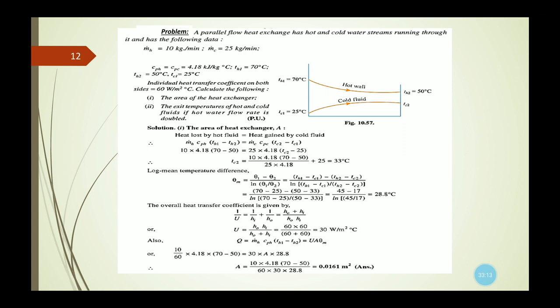Q can be represented mathematically in terms of the hot fluid parameters as m dot h cph into Th1 minus Th2, and also written in terms of the LMTD as UA theta m. From this equation we can calculate the area of the heat exchanger, which we get as 0.0161 meters square.